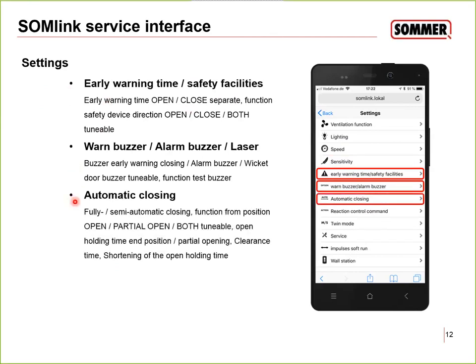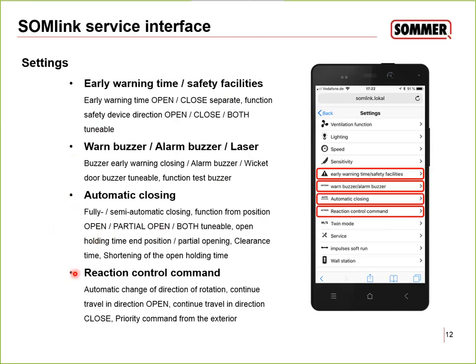Automatic closing: here you can set up whether you want fully or semi-automatic closing. You can even set the function from the partial opening position to have an automatic closing. Of course, you can set the time after which the operator should close the door. Then the reaction to a control command: what should the reaction be, continue travel in the same direction or close. Several reactions to the control command can be set up over here.